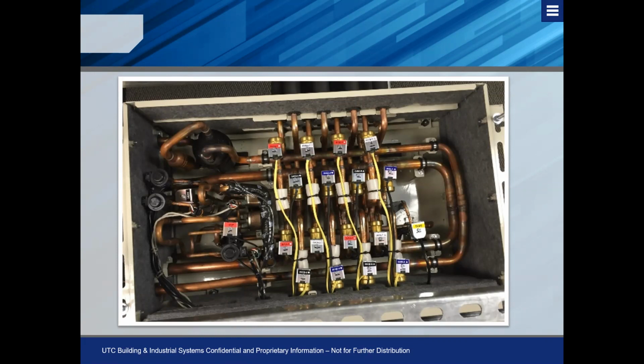So in this case, when we break this box down, there's that gas liquid separator where we create those 3 states of refrigerant: hot gas, liquid, and suction. Our braze plate heat exchanger subcools that liquid refrigerant so that we can get greater piping distances in the cooling mode, and also, generally speaking, because this box is typically centrally located and we pipe out from that central location, we certainly need to facilitate long piping runs. And then finally, we have our individual solenoid valves. So we have hot gas solenoid valves, liquid solenoid valves, and suction solenoid valves. And of course, depending on what each indoor unit needs is how those valves will open and or close. But basically, this is what our MDCs or our flow selector boxes are made of: gas liquid separator, braze plate heat exchanger, individual solenoid valves.